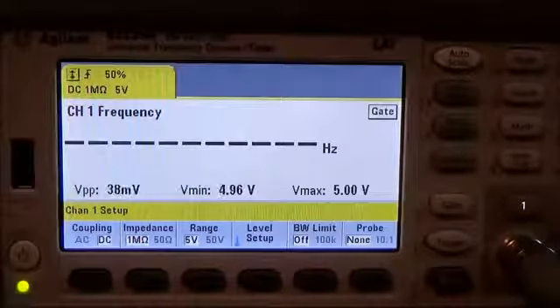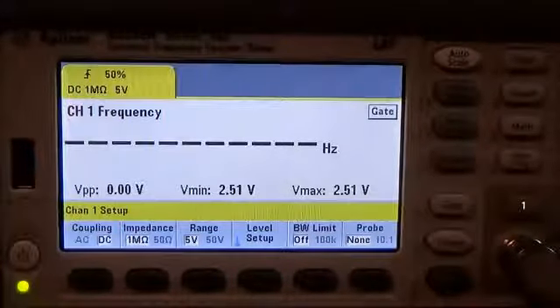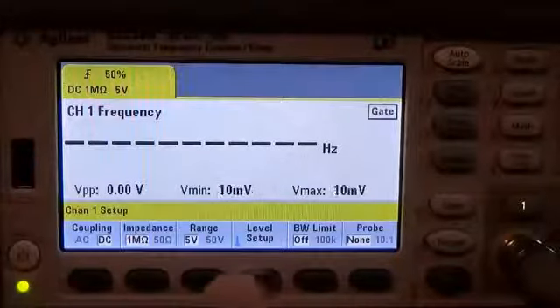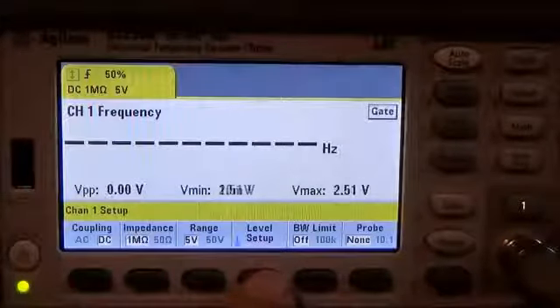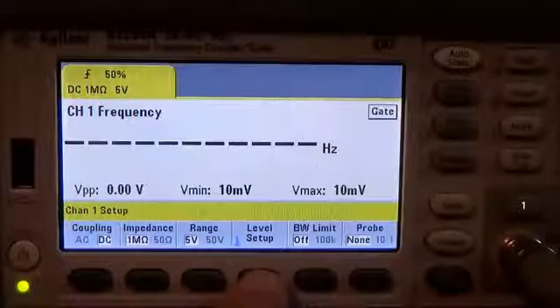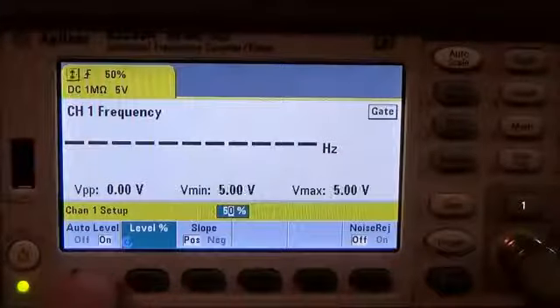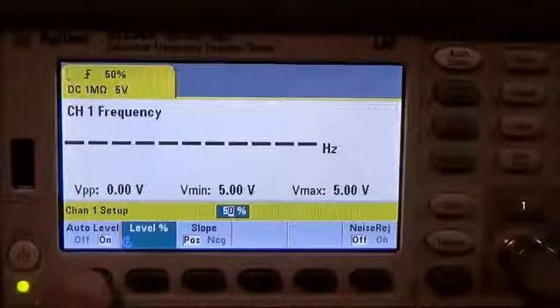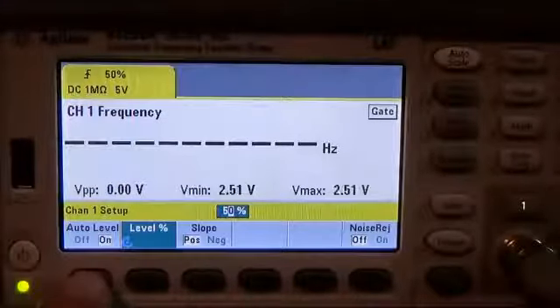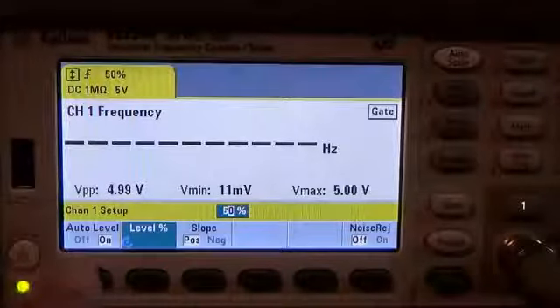Okay, the second thing that we want to note on the same set of soft keys on the input section is the level setup. We want to make sure that for low frequency signals we actually turn off auto leveling. It's only good down to 50 hertz. So for signals below that it may or may not detect.